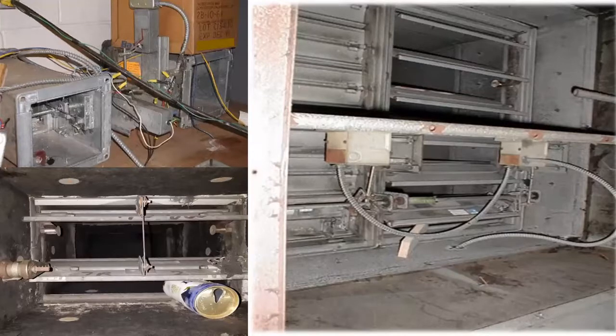Top left, you can see, and this is a retrofit picture where someone sends us and wants an actuator. And I'm like, you're gonna put my actuator in that fire trap? I really don't want it. But they need to clean that up. You can see how bad it is. The bottom one is the archetypical beer can or board and the damper. And that is a certified 1976 beer can. And I got that picture about 2 years ago. So that damper's been sitting there non-functional for how many years? I don't know. On the right side, there's the board holding the damper open. The actuators or the motors can be replaced easily. You just got to know what you're looking at. Next.